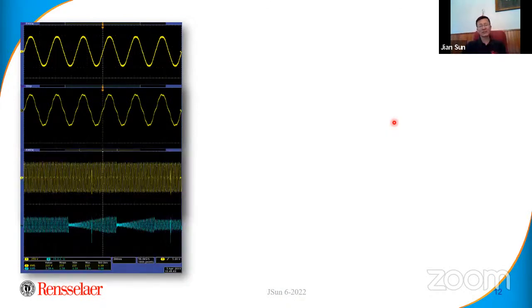When we further change the grid condition, the inverter disconnects because stability can't be maintained. The diagram shows the inverter operating for some cycles, then losing stability, shutting down, and starting over again. That's the problem we're talking about. For a single inverter shutting down, it doesn't matter much, but if all the converters do that, it's certainly not acceptable. These are the kinds of measurements we did in the lab.